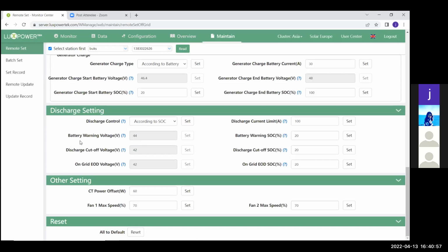Now, battery warning voltage, that's only to give you a warning if your battery is at a certain level. Discharge cutoff voltage, that's the setting where my inverter will completely stop using battery power. My inverter will switch off at this point.